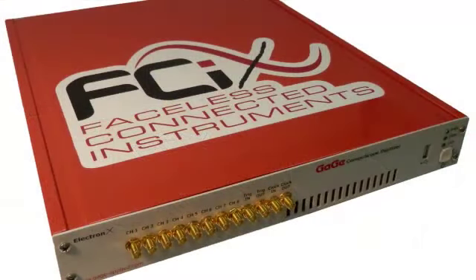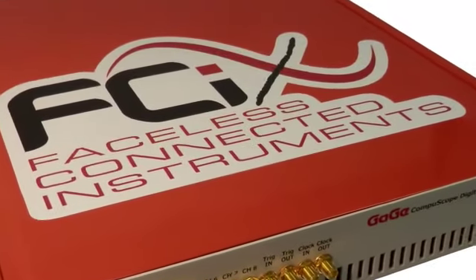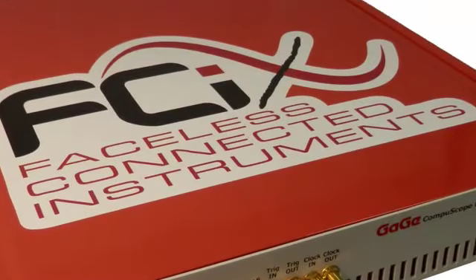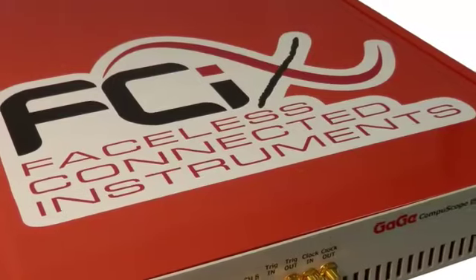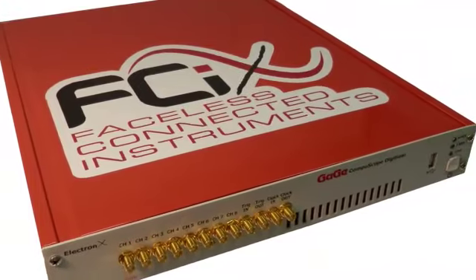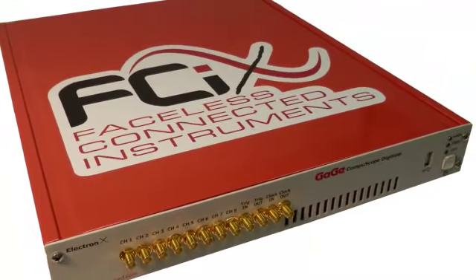This is an 8-channel GaGe FCI-X unit. As you can see, FCI stands for Faceless Connected Instrument. By instrument, we mean that the unit is a high-performance standalone oscilloscope. But unlike a conventional oscilloscope, it's faceless. By faceless, we mean that it doesn't have a built-in display, nor does it have any controlling knobs.